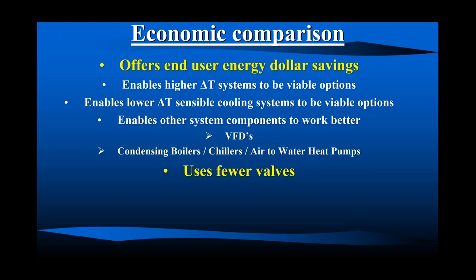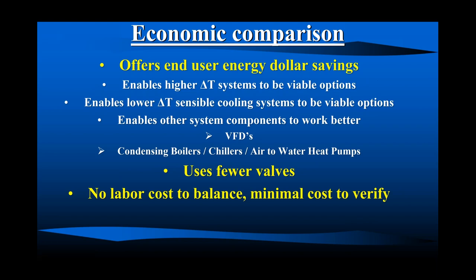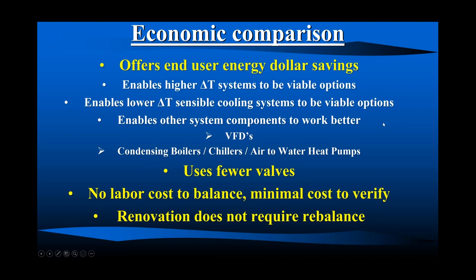If it's designed correctly, manual valves have to be on every T. No labor cost to balance. It's an automatic flow balancing valve. If you'd like to verify that it's doing its job, yes, you can hook up a meter to it. If you had an automatic flow balancing system and you added a new zone, you don't have to touch anything else. You just add that new zone with an automatic flow balancing valve without knocking on office doors saying, I have to get to your terminal unit to rebalance the manual valve.